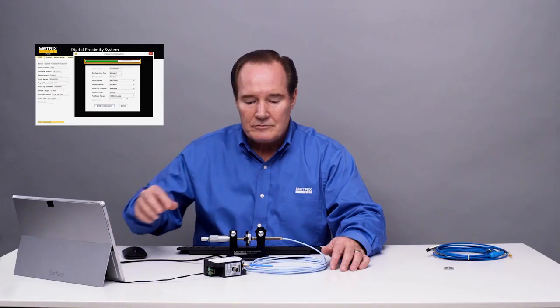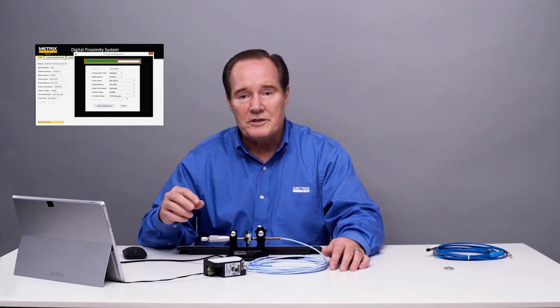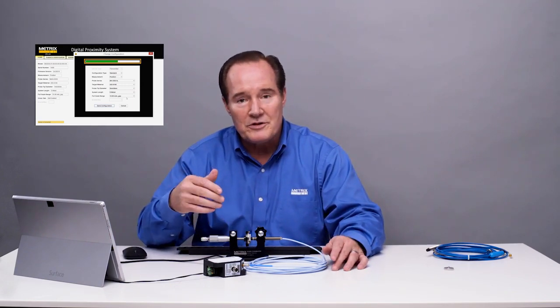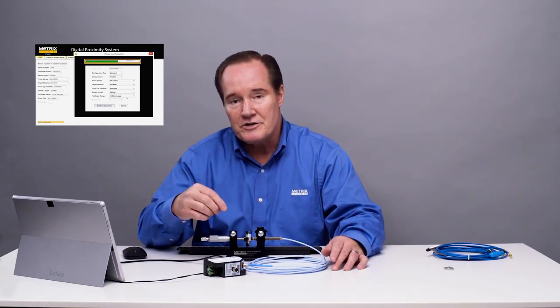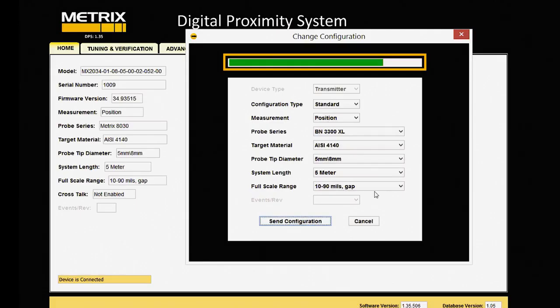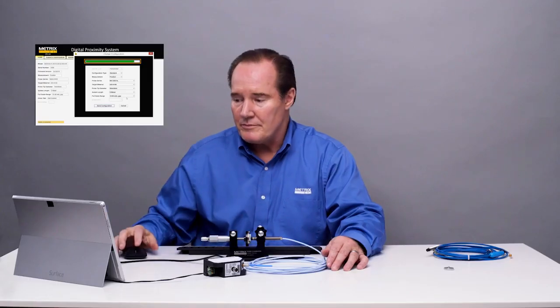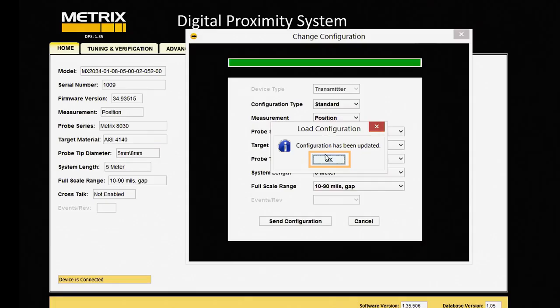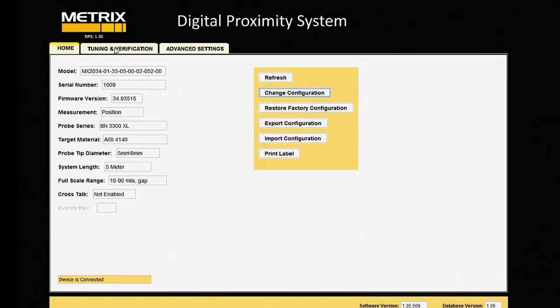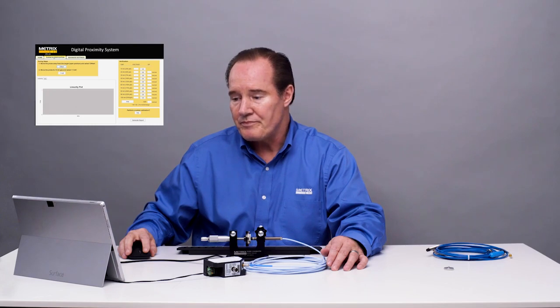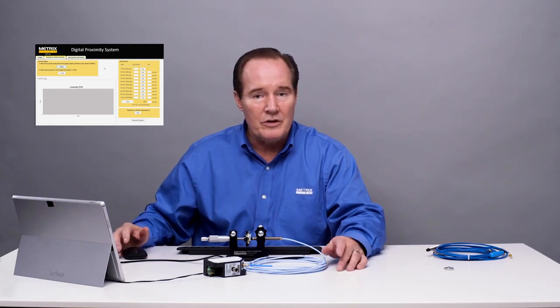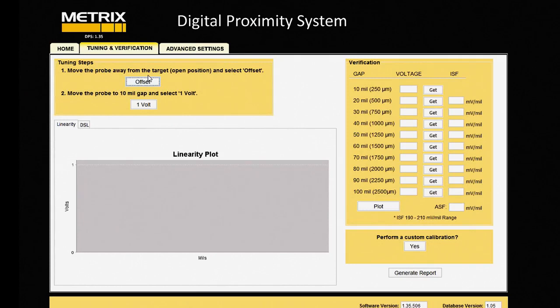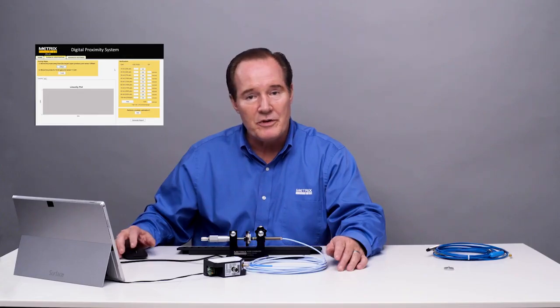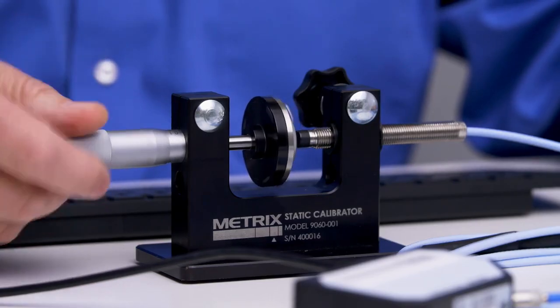Okay, now the digital proximity system is set for this probe and cable system, and we're going to check for its linearity. So we're going to use the tuning and verification tab to do that. So we'll let the configuration go through, and then we'll go to tuning and verification. And we'll do what the tuning and verification says. We'll do the offset and the 1 volt tests, and then we'll do the verification to see if we have linearity. If we don't, we'll do a custom calibration. Well, first I'll do offset.